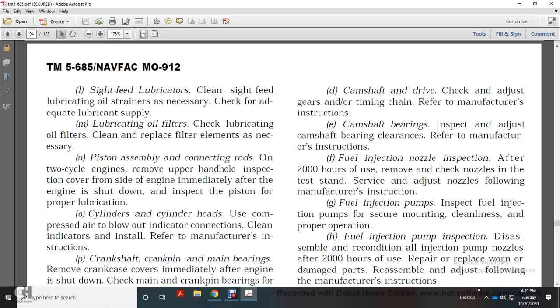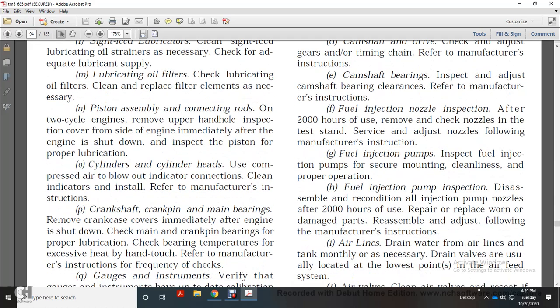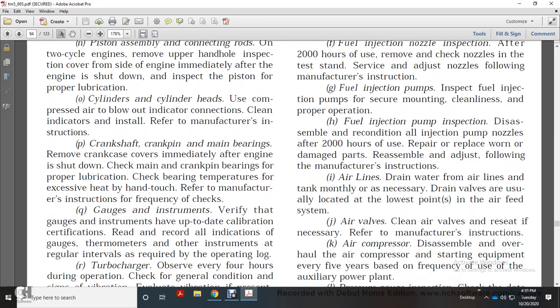Fuel injection pump: inspect the fuel injection pump, securing the mounting and checking for cleanliness and proper operation. Fuel injection pump inspection: disassembly and reconditioning of the injection pump and nozzle after 2,000 hours. Repair and replace worn or damaged parts. Reassemble and adjust following the manufacturer's instructions.